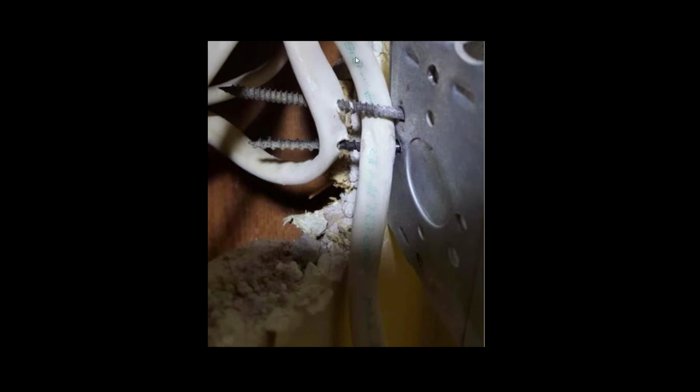We're looking at the wall here. Yes. This is the hole for the box, and you pulled the box out of the hole. Right. Well, it was loose because the screws weren't touching nothing. Right. So we test all the outlets we could get to. When we test it and pull our tester out, if the box moves, it's loose, so then we got to put our hand and pull the tester so we don't pull the box completely out. We get down to the next one, we had no power, so when I come back over to this loose one, I lifted it out to look behind it because it's obviously very loose, and this is what we found.